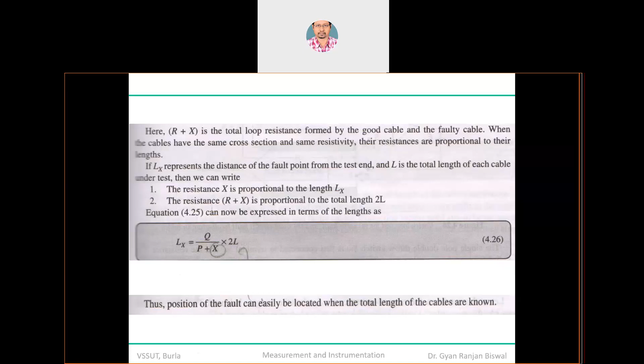Now you got the point why I encircled this x, because this should be q, this should not be p. So Lx is equal to q upon p plus q into 2L. That's how to identify the fault location when the total length of the cable is known. Next is the Varley loop test.